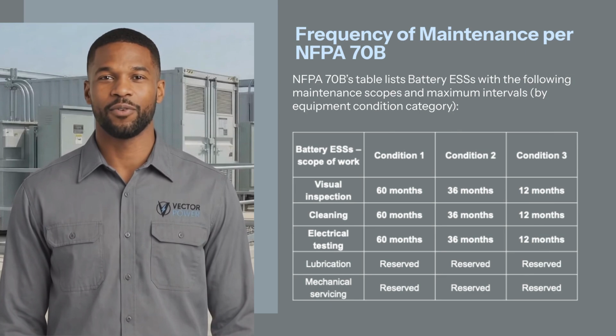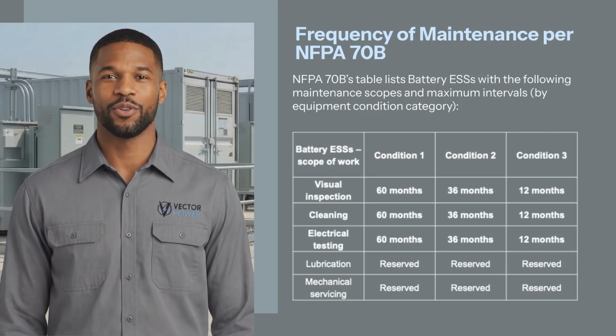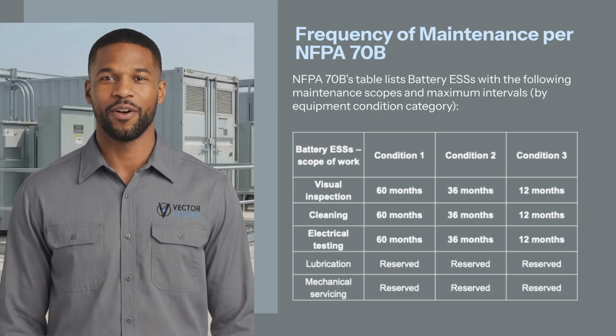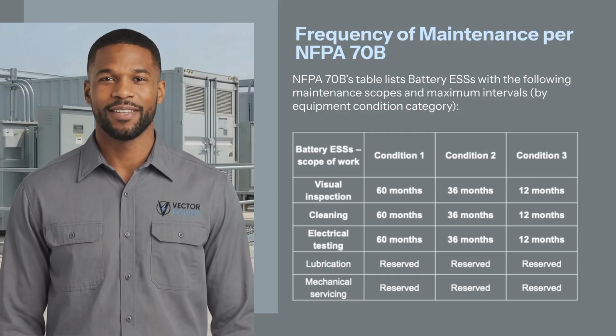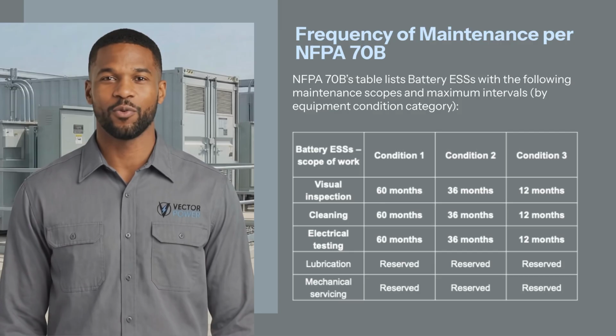NFPA 70B's table lists battery energy storage systems with the following maintenance scopes and maximum intervals by equipment condition category. Also applicable to a containerized battery energy storage system. Infrared thermography interval. Table 9.2.2 also includes an all-equipment line item for infrared thermography at 12 months for condition 1 and 2, and 6 months for condition 3. For a containerized battery energy storage system, this is commonly applied to accessible terminations and power components, for example, PCS inverter AC terminations, transformer connections, switchgear, DC disconnects where accessible and safe.